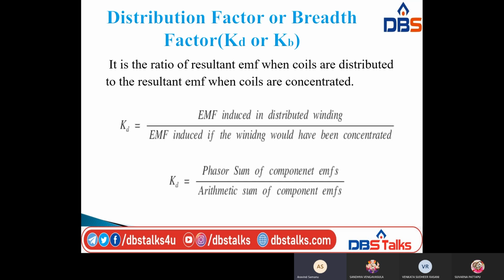So this is the indicating letter for the distribution factor, KD, that is equal to EMF induced in distributed winding by EMF induced in the winding if it would have been concentrated. This is the definition for distribution factor. Similar to the pitch factor, distribution factor has another definition, that is KD is equal to phasor sum of component EMFs by arithmetic sum of component EMFs. So here the phasor sum of component EMFs is equal to EMF induced in distributed winding, and arithmetic sum of component EMFs is equal to EMF induced in the concentrated windings.